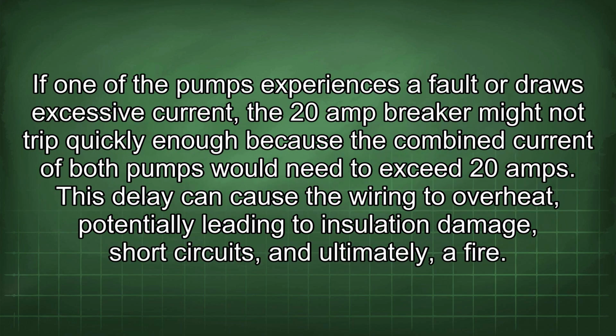If one of the pumps experiences a fault or draws excessive current, the 20 amp breaker might not trip quickly enough because the combined current of both pumps would need to exceed 20 amps. This delay can cause the wiring to overheat, potentially leading to insulation damage, short circuits, and ultimately a fire.